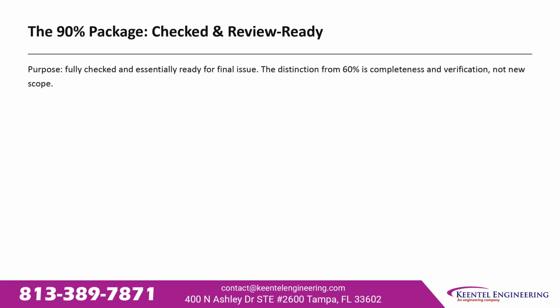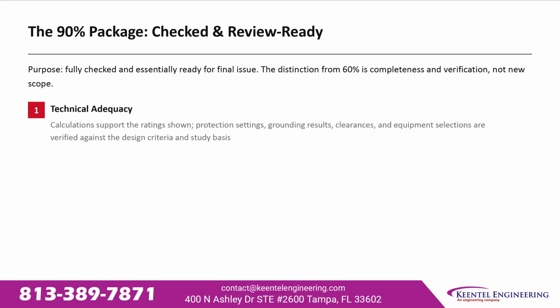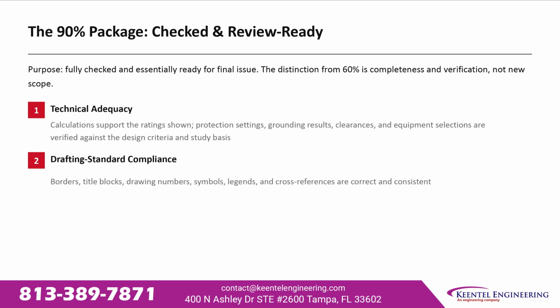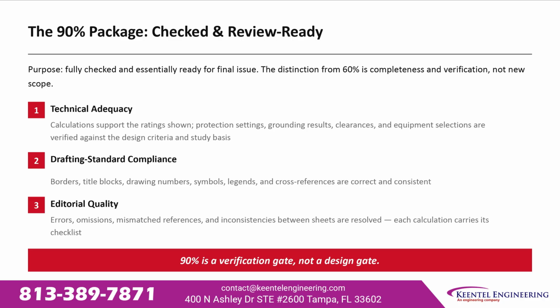The 90% package is fully checked and essentially ready for final issue. The distinction from 60% is completeness and verification, not new scope. 90% has 3 dimensions: technical adequacy, calculations support the ratings shown, and protection settings, grounding results, clearances, and equipment selections are verified against the design criteria. Drafting standard compliance, borders, title blocks, drawing numbers, symbols, and cross-references are correct and consistent. Editorial quality, errors, omissions, and inconsistencies between sheets are resolved, and each calculation carries its checklist. 90% is a verification gate, not a design gate. If new engineering is appearing at 90%, the 60% package was not complete.